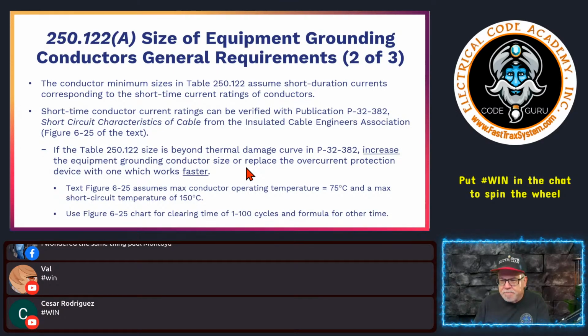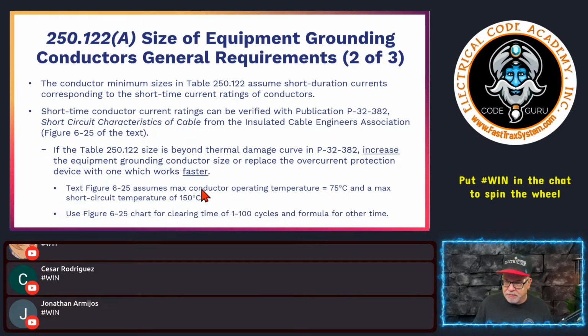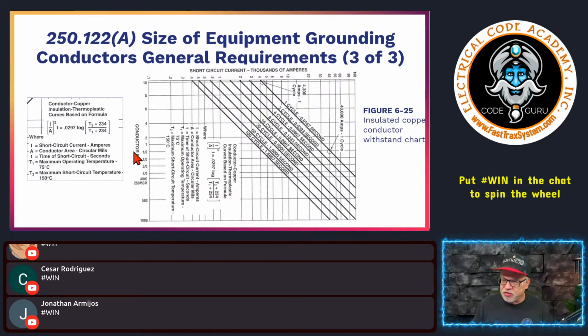Follow the NEC. My concern is that Code Panel 5 did not, when they brought up in the middle of the night the change to this rule about equipment ground conductors, that they even opened up this document and looked at it. That was my concern. I don't think they looked at this at all. Okay, but that ship has sailed, and that's what's coming for the 2026. So, it is what it is. Okay. Oh, here's that curve. Here's that sheet right here.